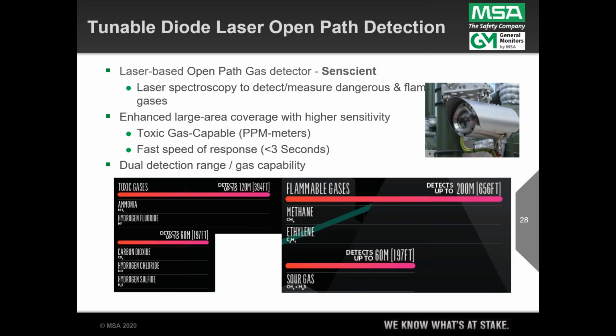And on the left side, I've got a listing here. We've got up to 120 meters. This system can detect ammonia vapors, hydrogen fluoride vapors. It can also sense carbon dioxide, hydrogen chloride, and hydrogen sulfide gases up to 60 meters in length. It can do flammables out to 200 meters. Again, its strength is these toxics, and we've got a dual range capable device as well.